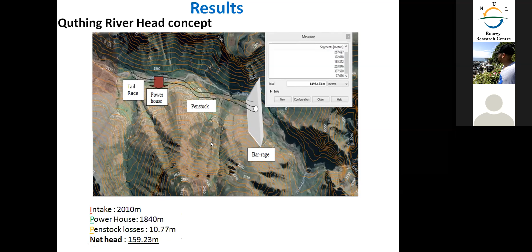Now with the head and flow rate determined for both catchments, the next thing that can be determined is the hydraulic power. Applying the typical formula, the hydraulic power for Quthing River is 906 kilowatts, and for Letseng-la-Letsie, 246 kilowatts, shown by this red graph here.